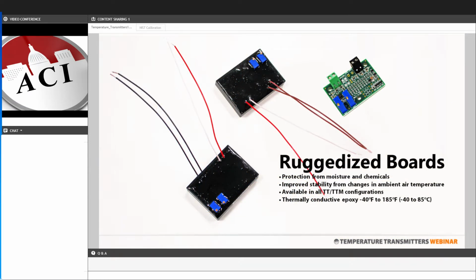Some of the specialty and custom configurations that we can do that you may not be familiar with include our ruggedized temperature transmitter boards. Here in the top right, you see what a standard temp transmitter board looks like. We have the ability to ruggedize these by soldering the lead wires directly to the board instead of using terminal blocks, and then covering the entire board with epoxy to provide an advanced level of protection from moisture, chemicals and particulates. These ruggedized, also known as potted boards, are available in all of the standard TT or TTM configurations.